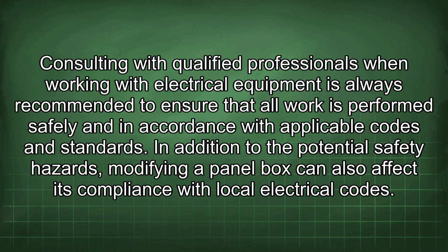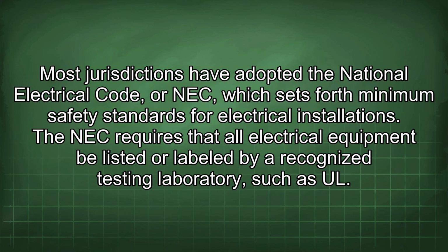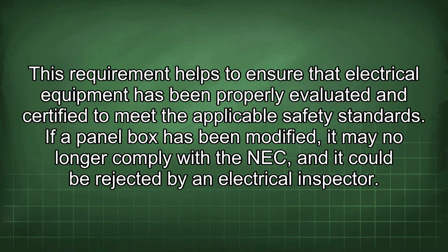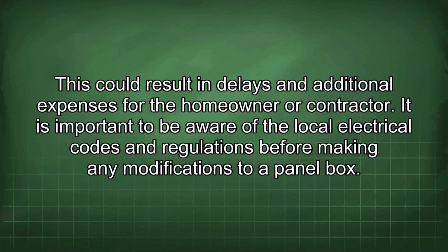In addition to the potential safety hazards, modifying a panel box can also affect its compliance with local electrical codes. Most jurisdictions have adopted the National Electrical Code, or NEC, which sets forth minimum safety standards for electrical installations. The NEC requires that all electrical equipment be listed or labeled by a recognized testing laboratory, such as UL. This requirement helps to ensure that electrical equipment has been properly evaluated and certified to meet the applicable safety standards. If a panel box has been modified, it may no longer comply with the NEC and it could be rejected by an electrical inspector. This could result in delays and additional expenses for the homeowner or contractor.